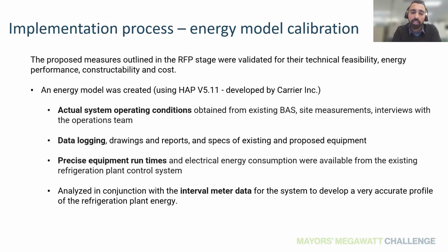Also, really analyzing the refrigeration plant data made us realize there's a lot of optimization that can be done on the current operation, including improved ice temperature set points, improved return brine set points, as well as finding issues with the suction pressure.